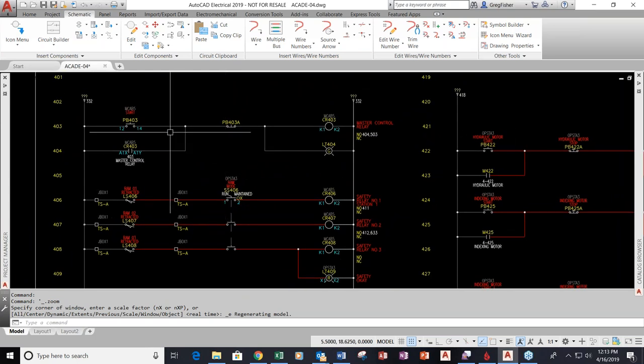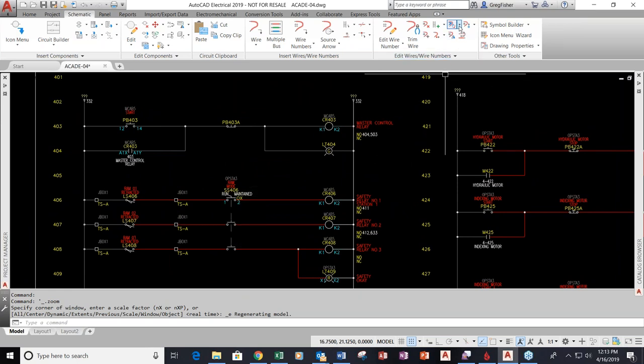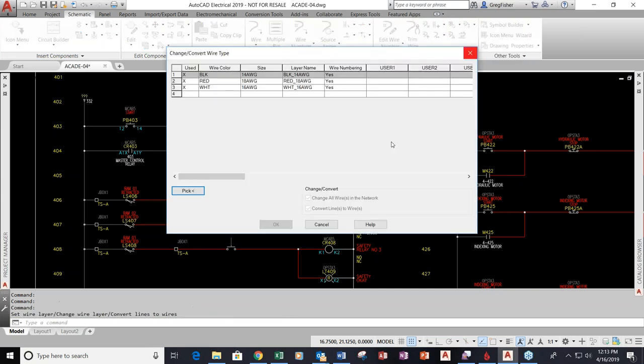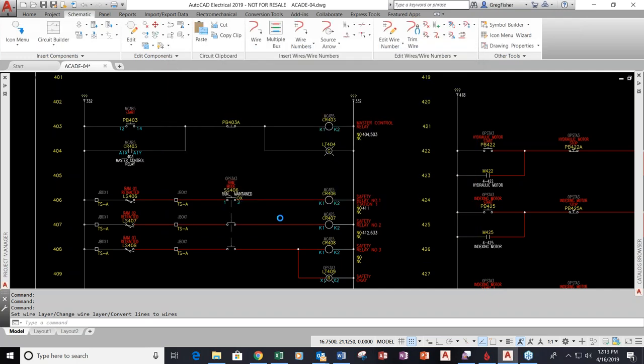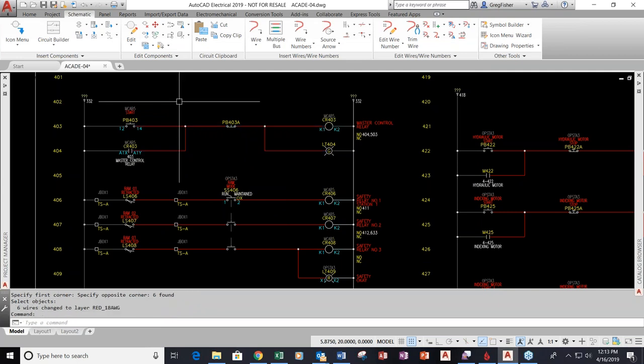As you can see, the wires I dropped down here don't match the size or color of the ones below. I can go to my change/convert wire type command. When you draw wires inside AutoCAD Electrical, it knows it's a wire based on the layer it's on. AutoCAD Electrical takes full advantage of using layers for different purposes. So if this wire should have been 18 red instead of 14 black, I'll select all of them and easily move them from one wire layer to another wire layer.